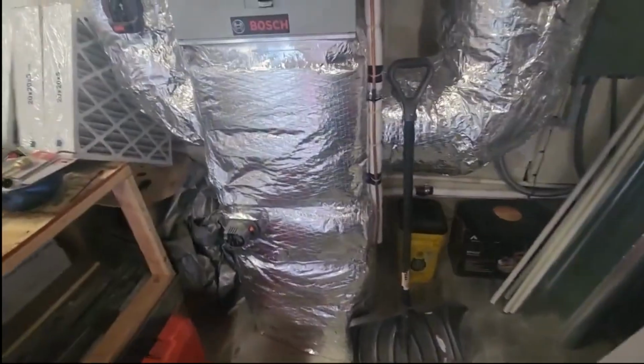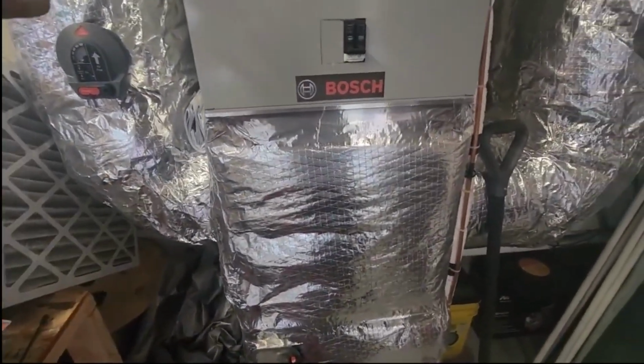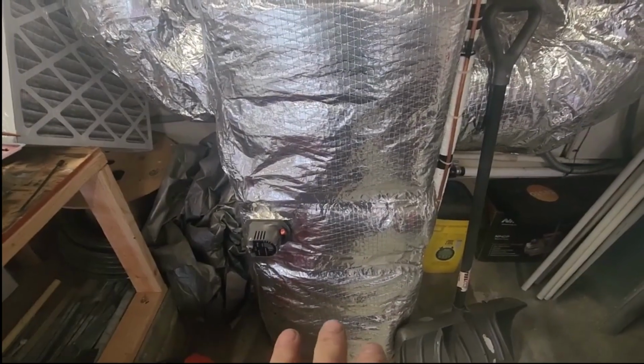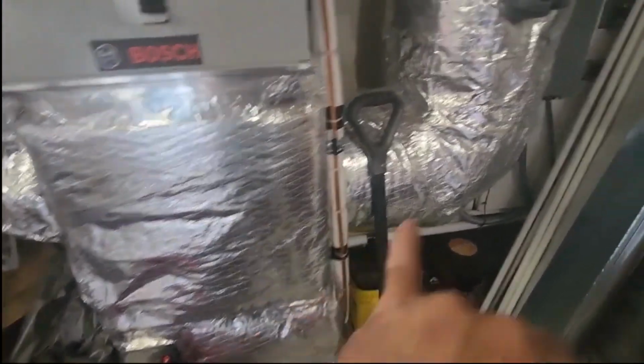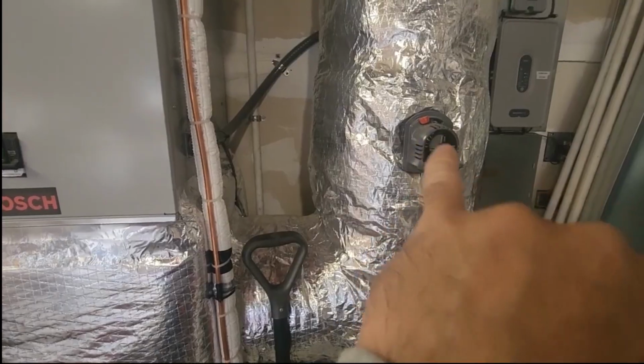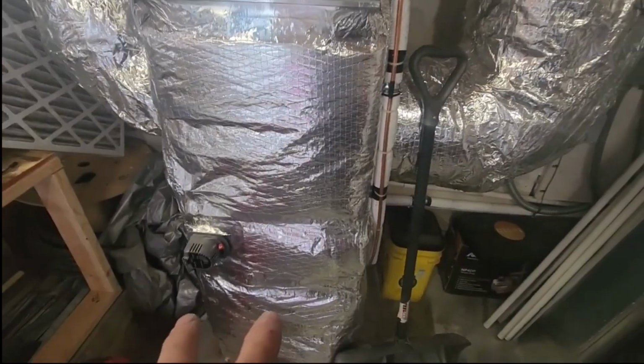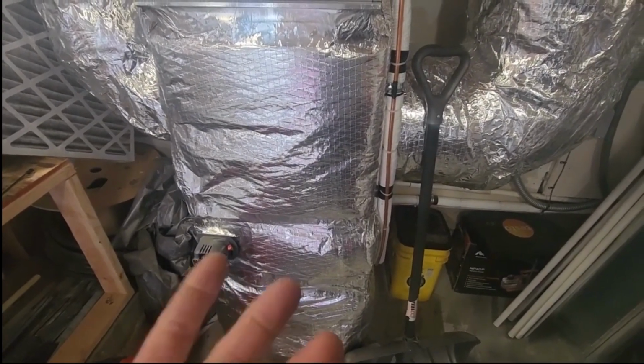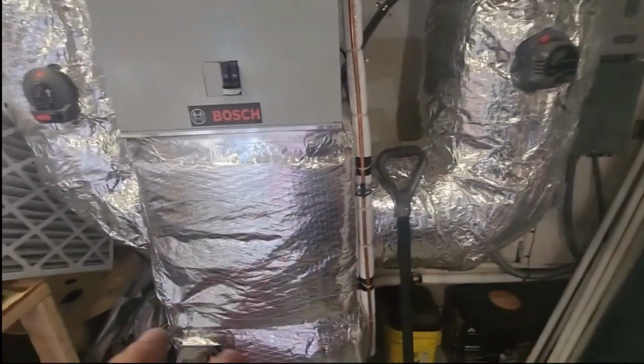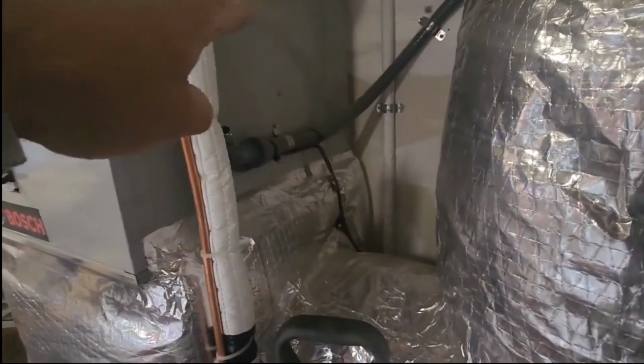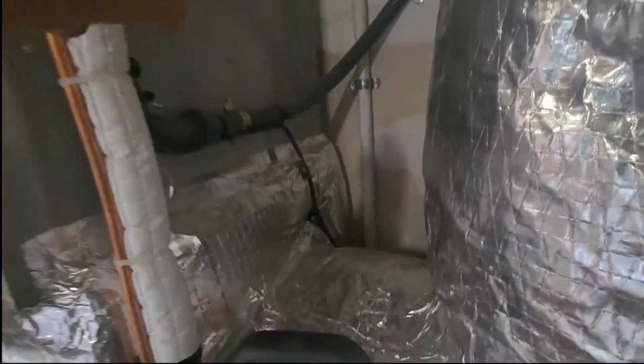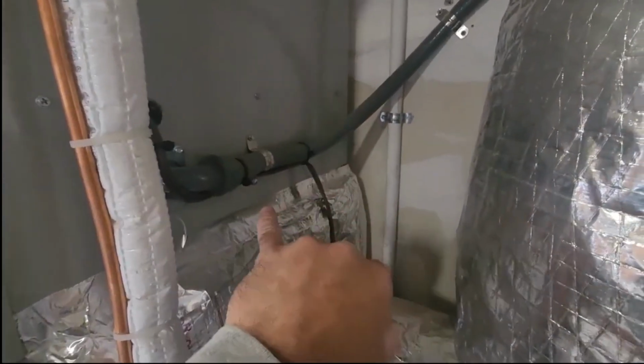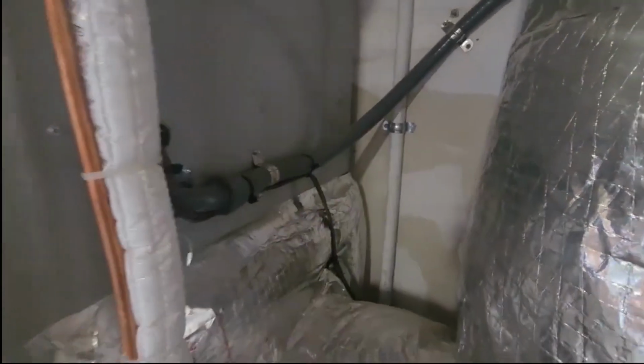Let me show you the orientation again on my system. I have my bypass here. I'm not worried about it because we're checking total static of the supply and return. There's the one damper there, and the other damper that goes upstairs, the supply run. I'm going to force this thing into high fan and put both zones into cool. On these air handlers you want to be past everything, right? We want to be as close to the furnace as possible, and the supply on these air handlers is back here. It only goes out to about here, so we make sure we get our static pressure tip in there, and then our return is self-explanatory.